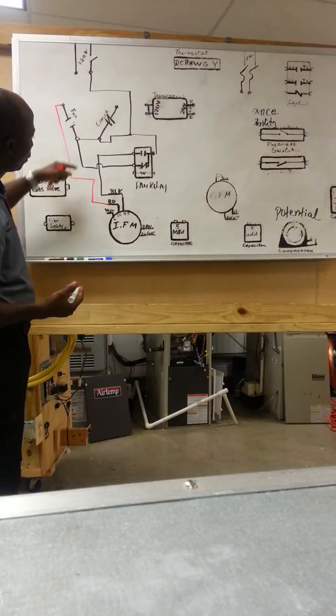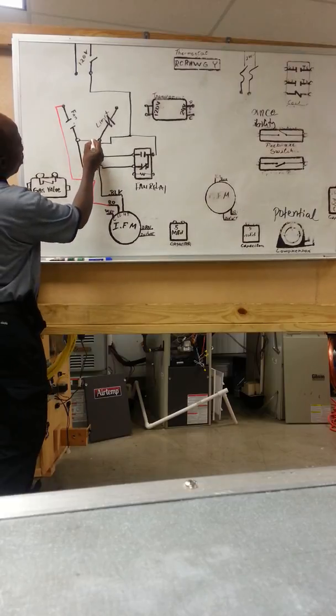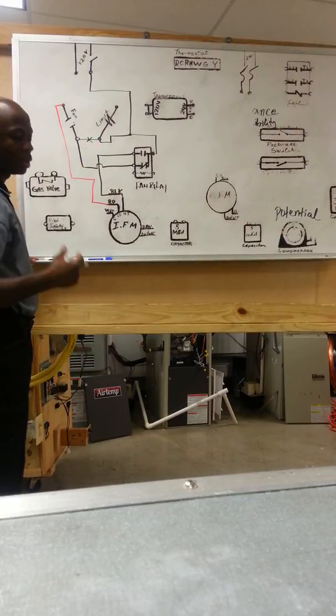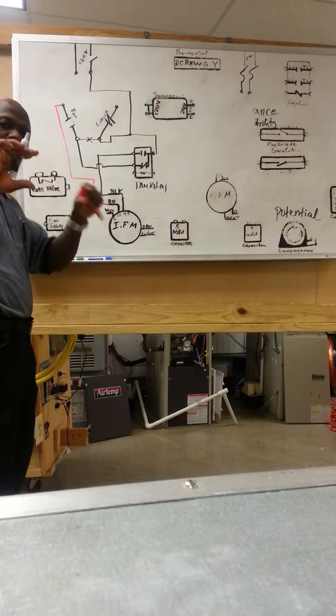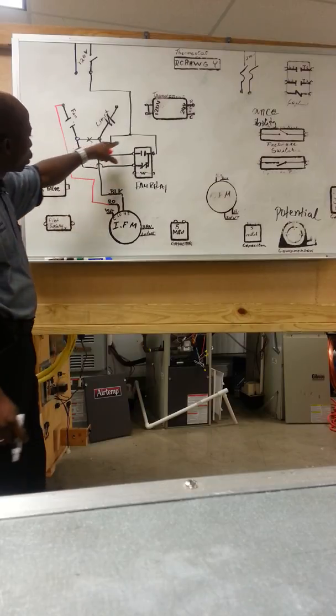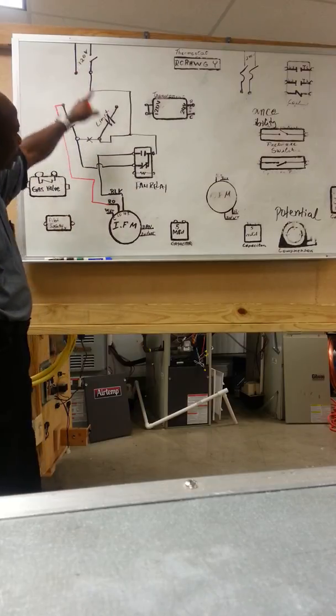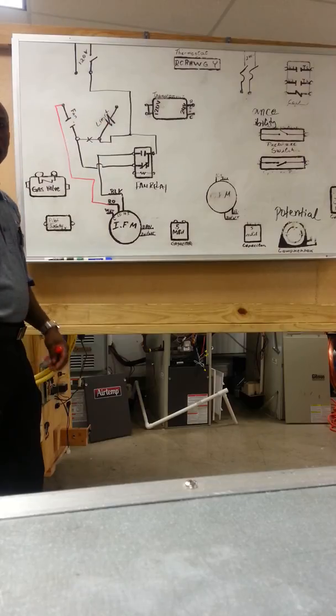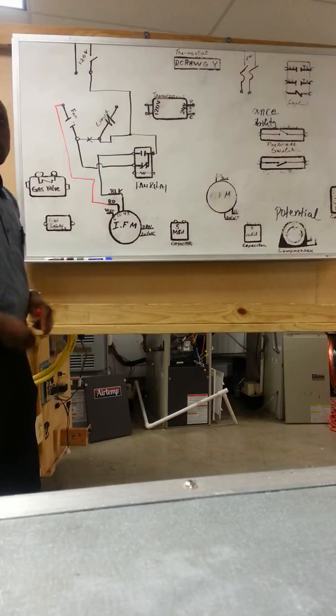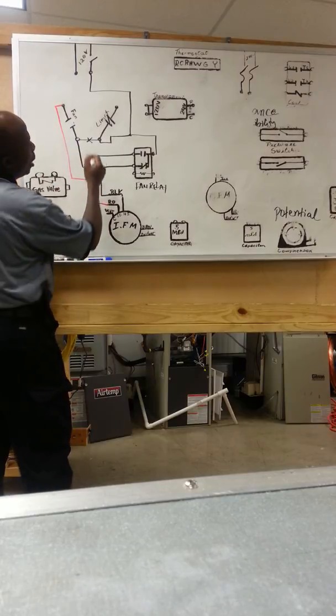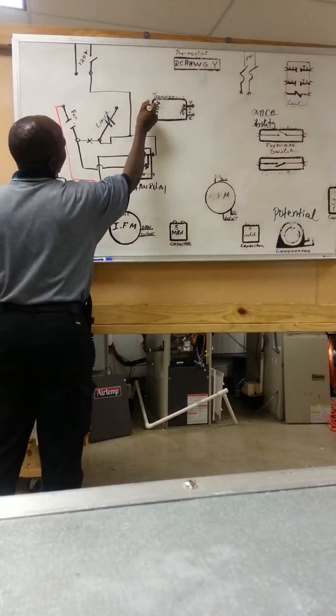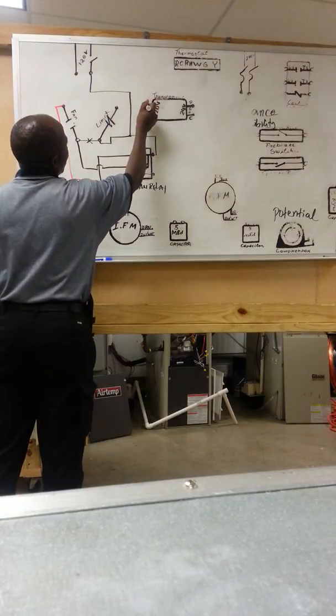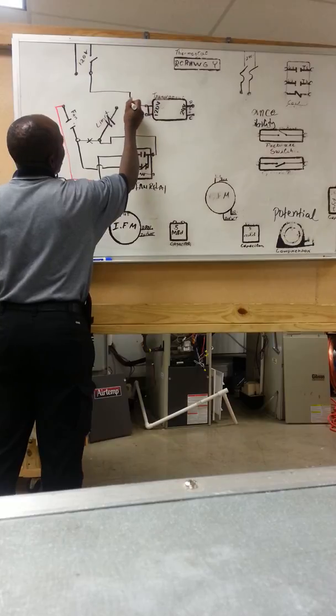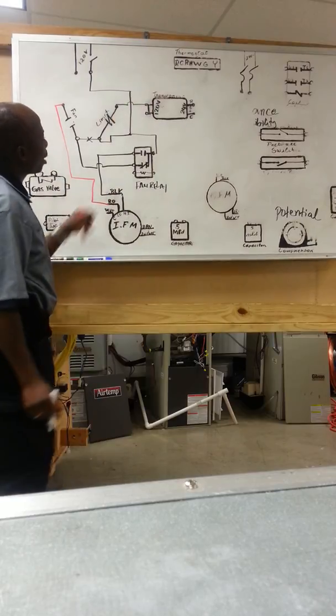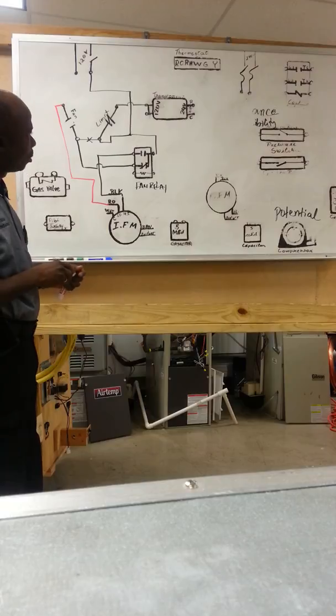But what I'm going to have to do here, just to be safe, is break this contact here, which is normally a bridge, a little brass tab in between. That's broken. So I got my power coming straight from the switch, feeding the normally closed side of the fan center, which is the limit switch. From the limits, I'm going to send power onto my transformer, 120 volts, which is going to be the black wire right here. I got the black wire coming into the transformer.